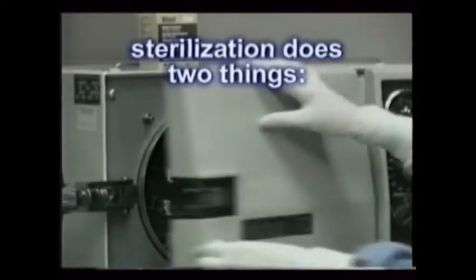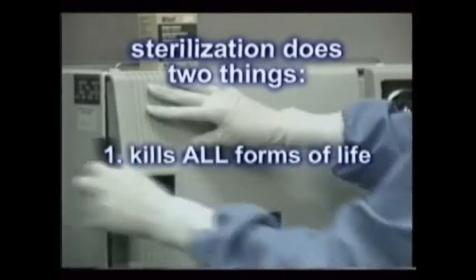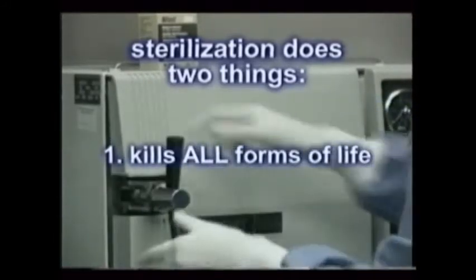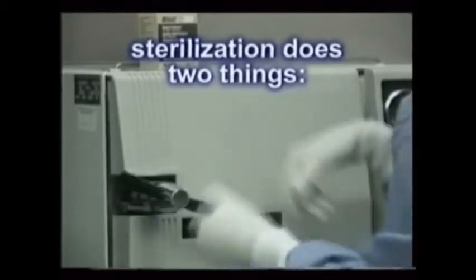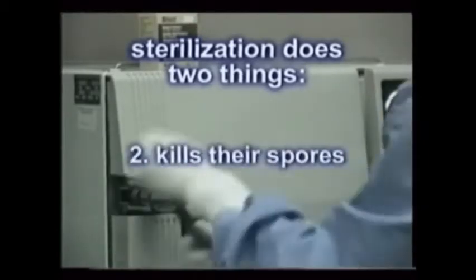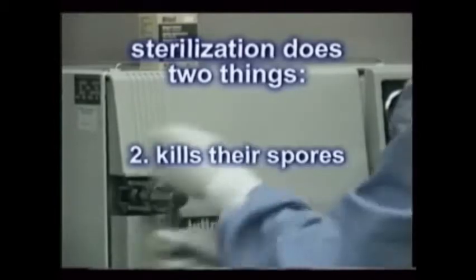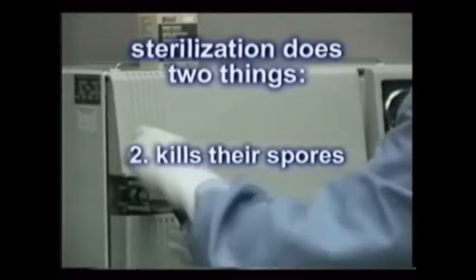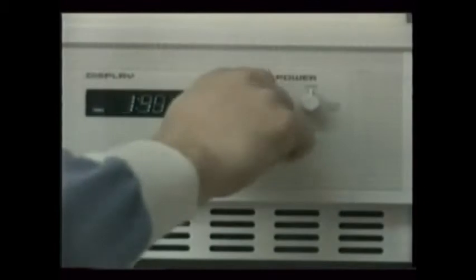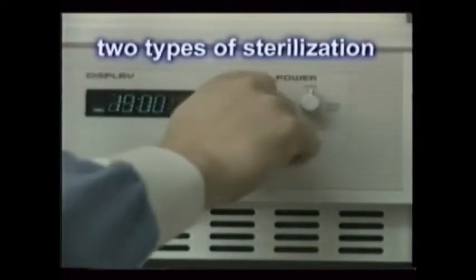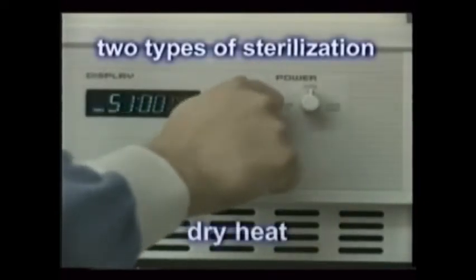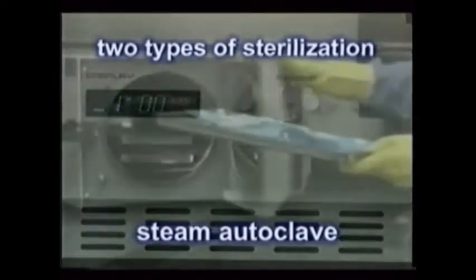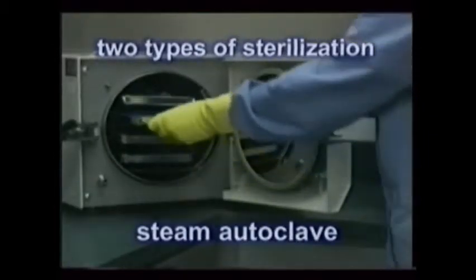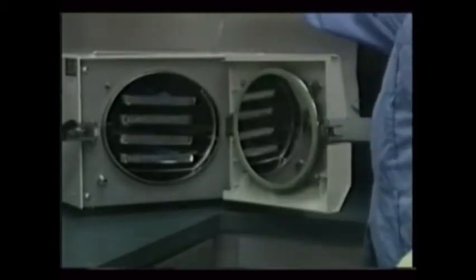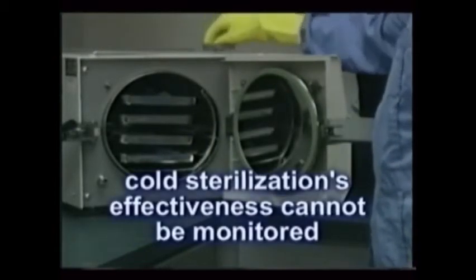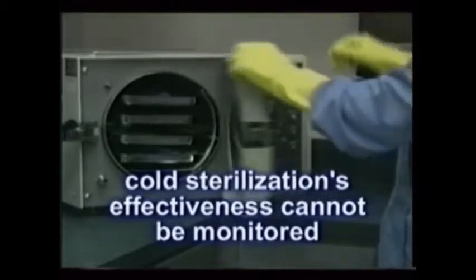Sterilization of the instruments does two things. First, it kills all forms of life on the instruments, within the packaging and inside the sterilization chamber. And second, it renders harmless all residual spores that may seed an infection later. Sterilization is accomplished by one of two methods, either dry heat or steam autoclave. While liquid cold sterilization was once used, it's no longer recommended since its effectiveness cannot be properly monitored.